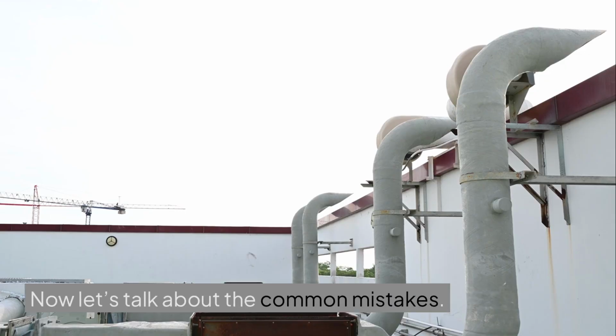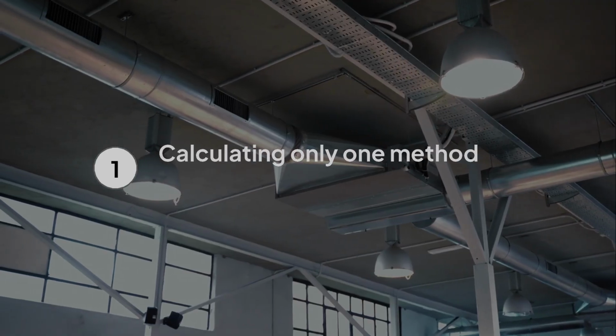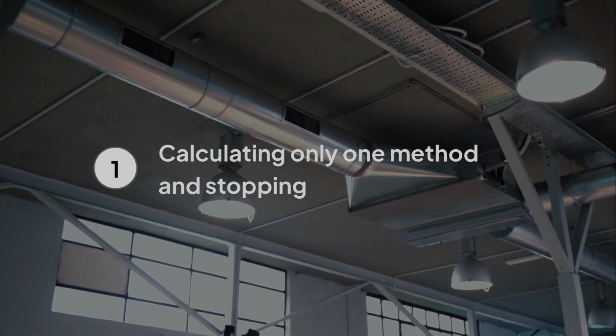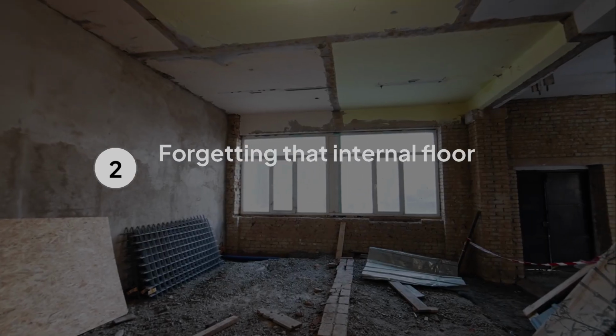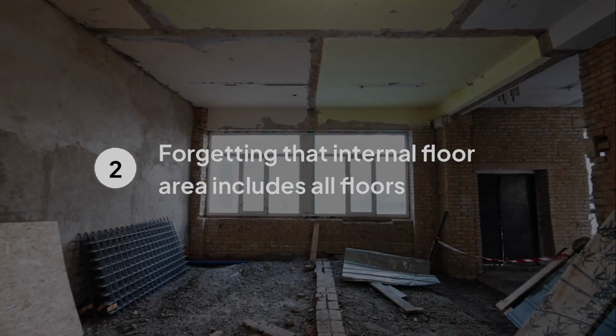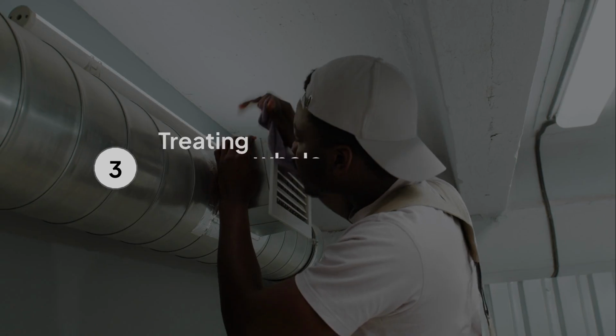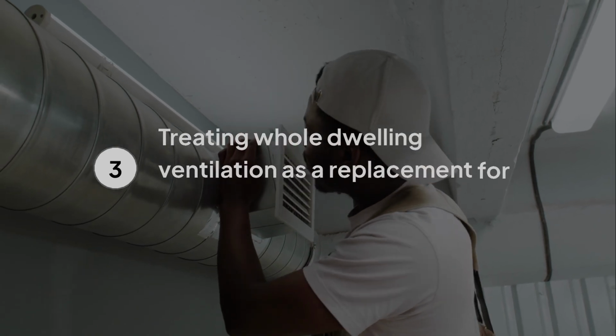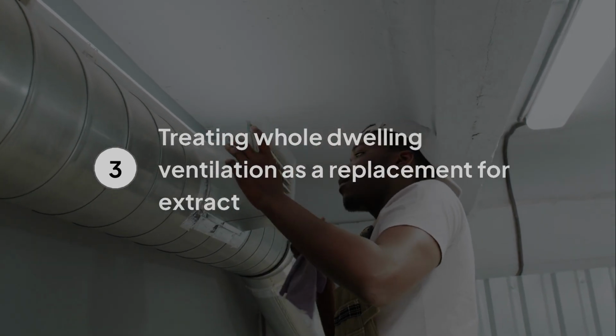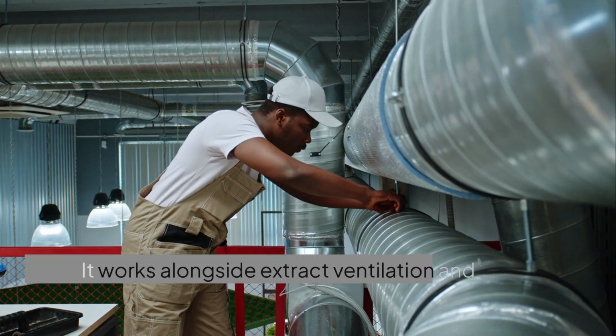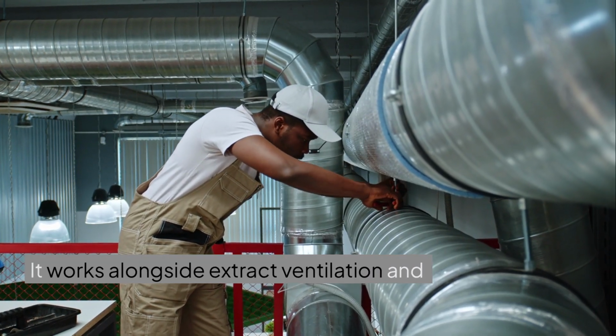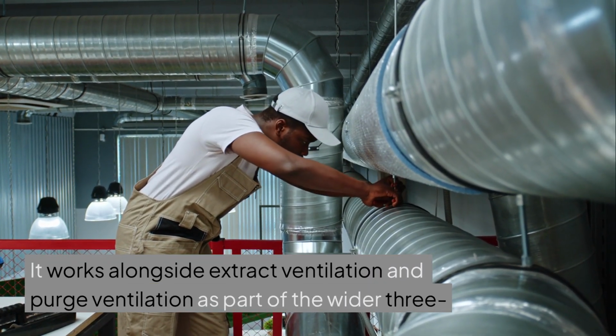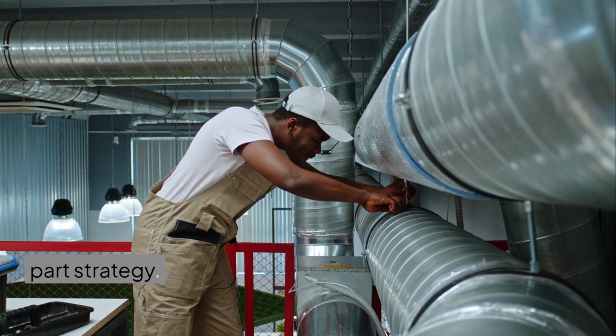Now let's talk about the common mistakes. The first mistake is calculating only one method and stopping. The second is forgetting that internal floor area includes all floors. The third is treating whole dwelling ventilation as though it replaces extract. It doesn't. It works alongside extract ventilation and purge ventilation as part of the wider three-part strategy.